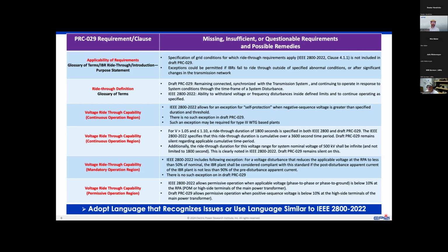In general, the applicability of requirements in 2800 is specified with some limitations for the grid conditions. There are exceptions that are permitted to allow IBRs to diverge from their ride-through when grid conditions are outside normal conditions that would be specified by the transmission operator. So those could be certain extreme contingencies, and the standard does not go as far as defining what the threshold for extreme contingencies is, under which the standard requirements may not apply anymore. But it does recognize that if you are in a contingency, maybe N-1 or N-x, you may not have the ability with that plant to stay connected.